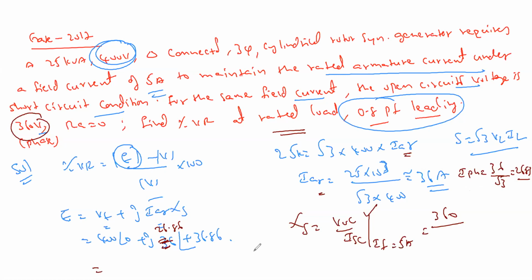And that's all - VOC by ISC, VOC is 360, ISC is the rated short circuit current of 26. Is this correct? 26, 36 by root 3, how much is it? Let's just check that one. I think something is off here, something is fishy.